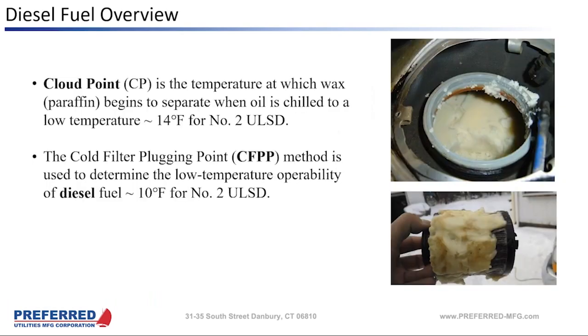So just some definitions. The cloud point is the temperature at which wax begins to separate when oil is chilled to a low temperature. It's usually about 14 degrees for ultra low sulfur diesel, depending on the blend. There's another standard, the cold filter plugging point, CFPP method, used to determine the low temperature operability of diesel fuel. It's usually around 10 degrees F for ultra low sulfur diesel.